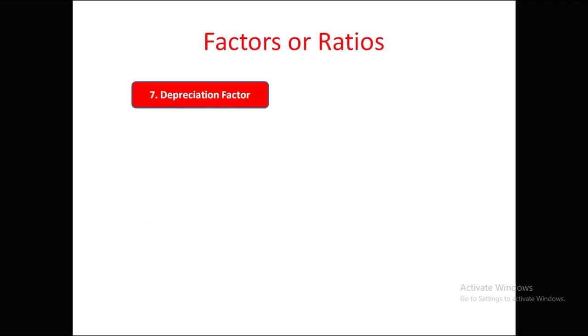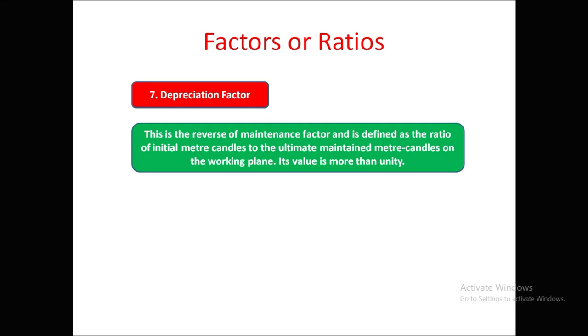Depreciation factor is the reverse of maintenance factor. It is defined as the ratio of initial meter candles to the ultimately maintained meter candles on the working plane. Its value is more than unity.